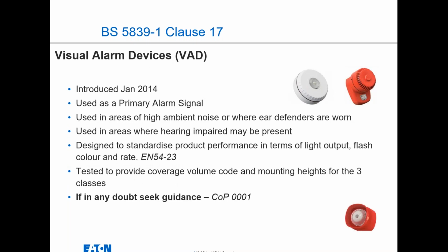So this particular standard, EN54 Part 23, came into effect back in 2014, and manufacturers had a huge problem trying to comply with it, and still some of them do now, because it's quite onerous. It's almost similar to that of the sound pressure levels. So light behaves in different ways, and again, it's very difficult to measure a flashing light in terms of its lumens and lux outputs. So you have to refer to manufacturers. That's the only way in design, is to look at the manufacturer's information and their technical data sheets to show how the light spreads.